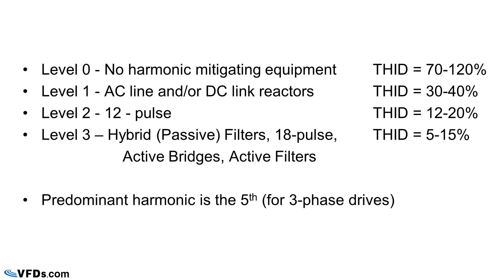There are many other methods of harmonic mitigation, and I've shown some of them here. I've divided them up into levels — these are simply my levels; they don't correspond to any sort of a standard — but you can see that there's a number of different harmonic technologies. You don't really need to understand them; you simply need to know how they perform. So without any reactors, we have 100% harmonics. With reactors, 30%. And then these others can get us down to 5% or even lower than 5%. This represents the amount of high-frequency noise generated into your power distribution system.